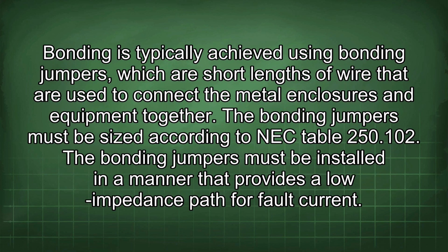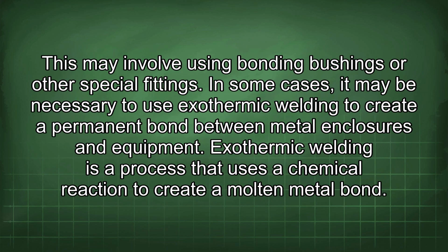Bonding is typically achieved using bonding jumpers, which are short lengths of wire that are used to connect the metal enclosures and equipment together. The bonding jumpers must be sized according to NEC Table 250.102. The bonding jumpers must be installed in a manner that provides a lower impedance path for fault current. This may involve using bonding bushings or other special fittings.